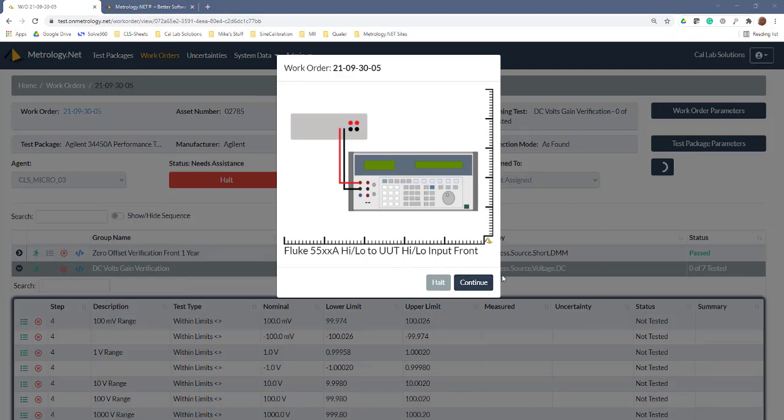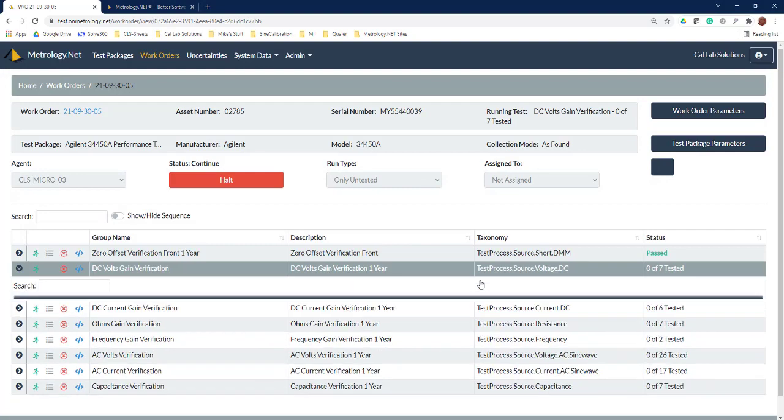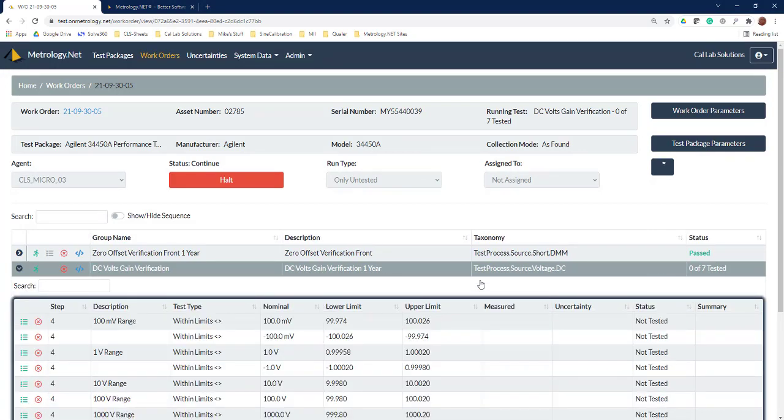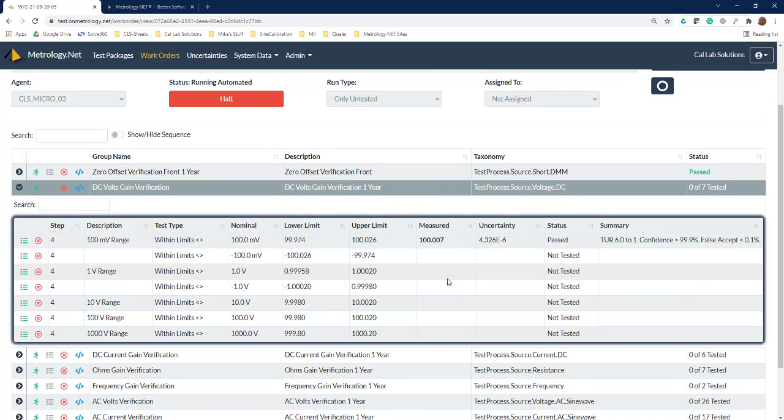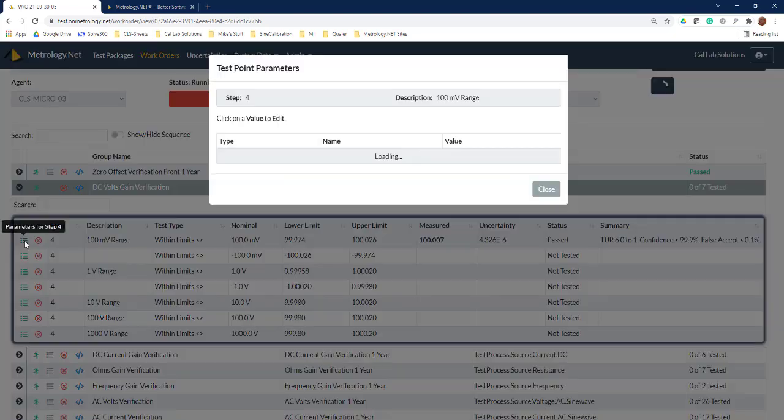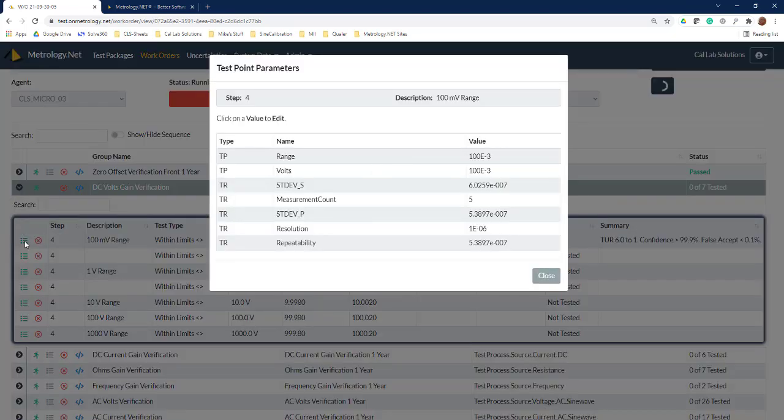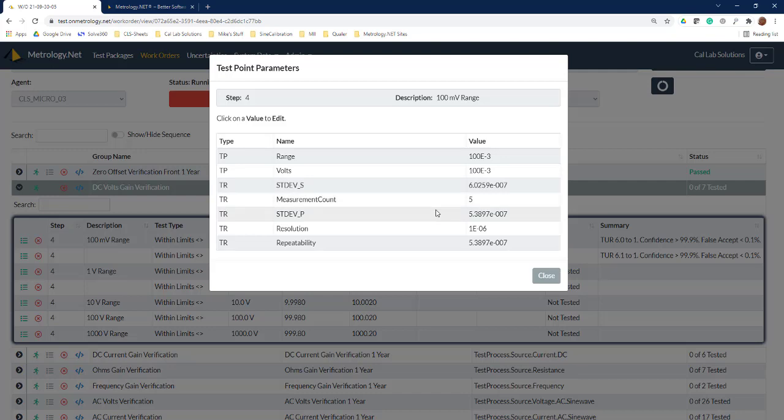Let's go ahead and connect it up. Now that we have it connected we can hit continue. Takes a few minutes for it to do five measurements at each data point, but you can see now we've got 100.007 here. Now if we click in here and open our parameters, we can see that we've got five measurements, we've got our standard deviation, we've got repeatability, we've got our resolution—so all of that gets pushed into our measurement uncertainty calculator.